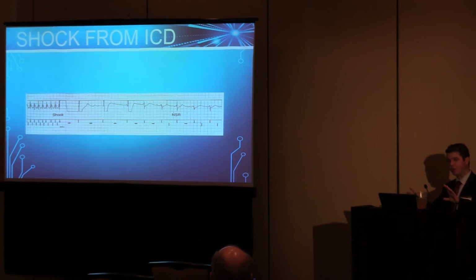you'll look at the bottom right-hand corner, particularly if you're dealing with a Medtronic device, like the programmer that she showed earlier, and it will give you an alert. If you click on that alert, it will tell you what's going on, that a shock was delivered. Many times you can see these EGMs, and you can look at it and just determine if the shock was delivered appropriately or not.